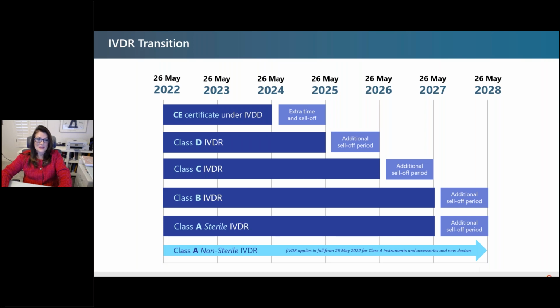Some of the reasons for the transition are that basically IVDs did not normally require notified body oversight. Currently, 8% of all IVDs, before the regulation goes into effect, needed a notified body. But with this new regulation, 80% are going to need a notified body review. So that means not only do they need to submit to the notified body, but they have to find one and apply to it. And as of October, there were 6. So it's not like the dozens with medical devices. So you really need to get in there and get that done.